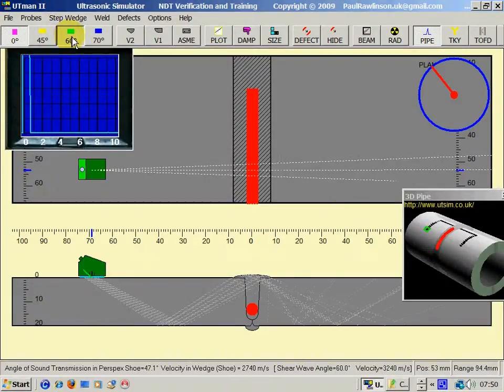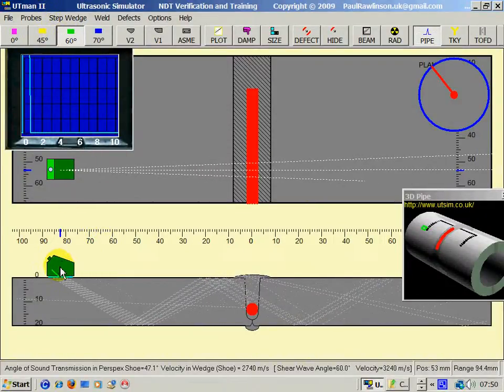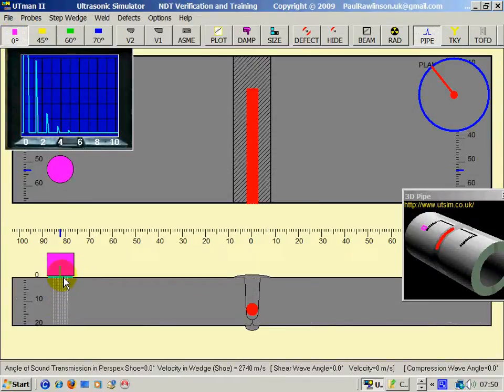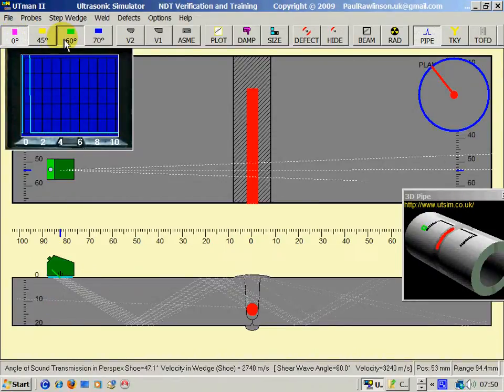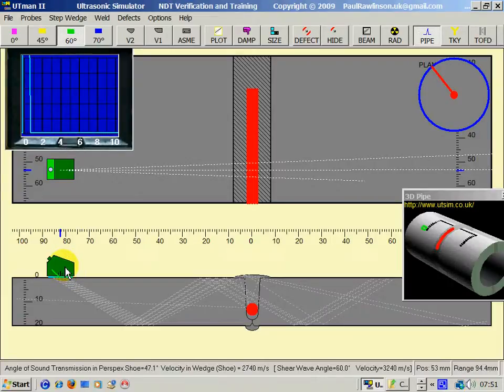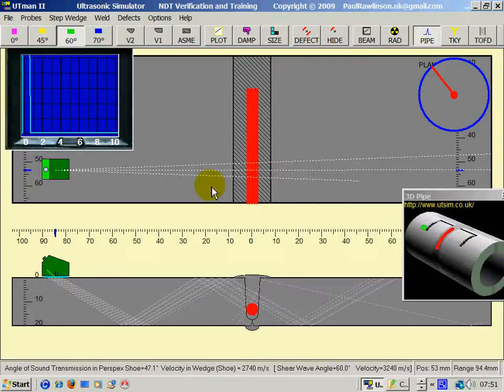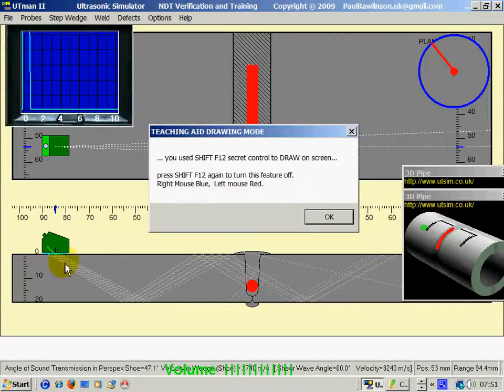Now, the angle probe, that is called shear wave. The zero is called compression wave. These angle probes are transmitting in shear wave. And here the wave is more of a wave, and in fact travels more like that. And it is approximately 3,000 metres per second in carbon steel.